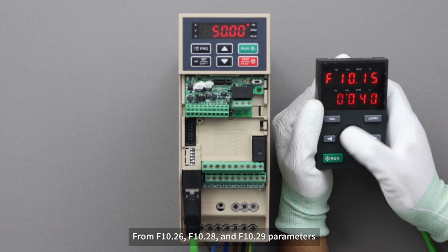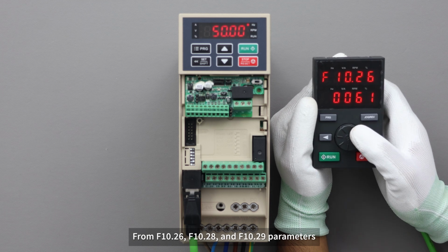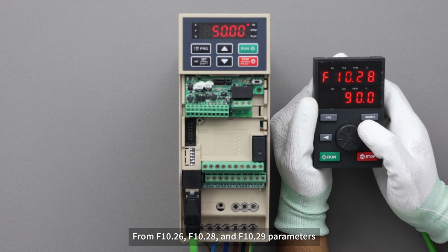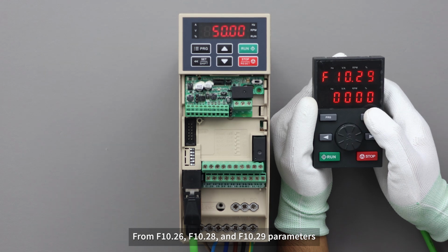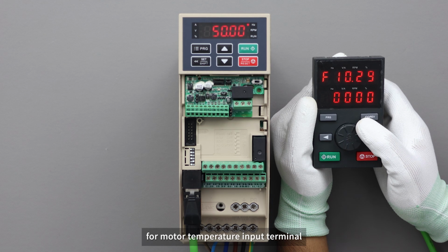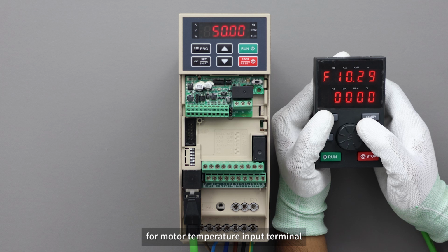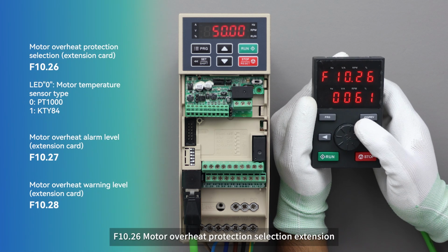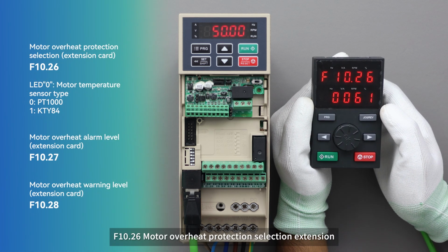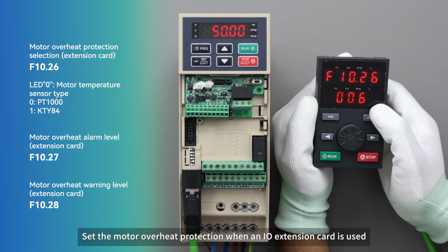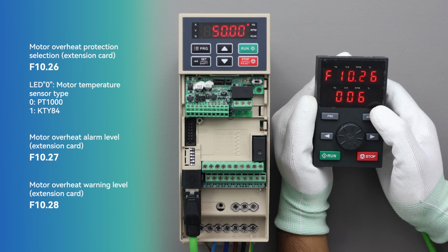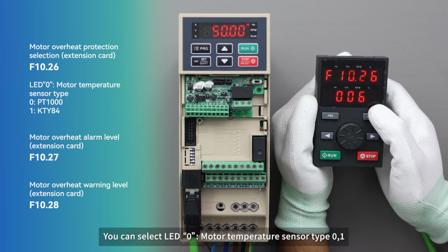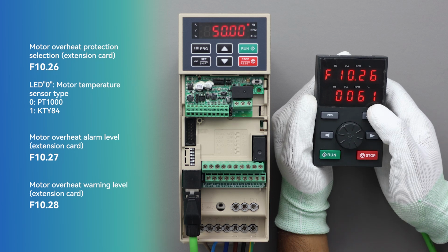From F10.26, F10.28 and F10.29 parameters for motor temperature input terminal. F10.26 motor overheat protection selection extension. Set the motor overheat protection when an I/O expansion card is used. You can select LED 0, motor temperature sensor type 0 or 1.